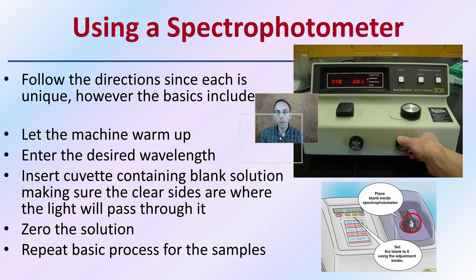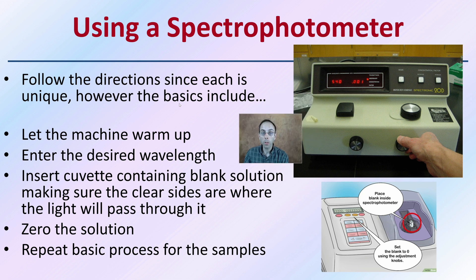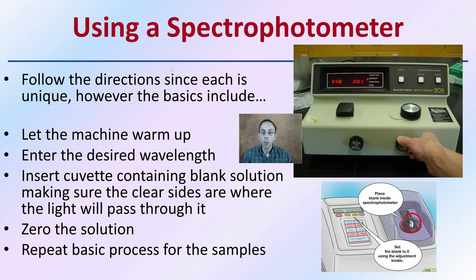When using the spectrophotometer, follow the directions since each machine is unique. However, the basics that apply to all of them are: let the machine warm up — this can be a short or long duration, so allow sufficient time. Enter the desired wavelength you're going to be studying. Insert the cuvette containing a blank solution, making sure the clear sides are where the light is passing through — you don't want to insert it the wrong way. Then zero that solution.